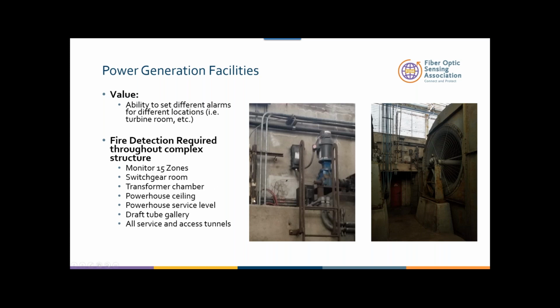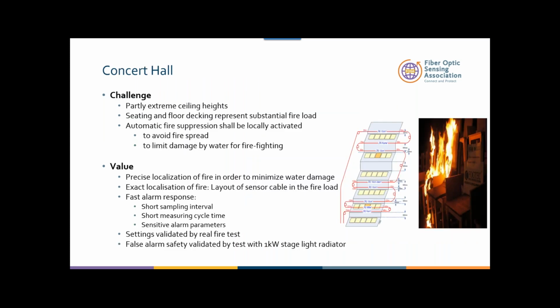In this picture, you can see the cable coming up to the structure, mounted horizontally, vertically this way, horizontally. We changed the alarm setting for this area because there is a motor running, and you're also going to the venting system, and there's a big fan, so we changed the alarm parameters there. The ability to buy a system and say, I don't know what the alarm level is going to be from a temperature point of view, and I can set it up on the go. That is the beauty of fiber optic linear detection.